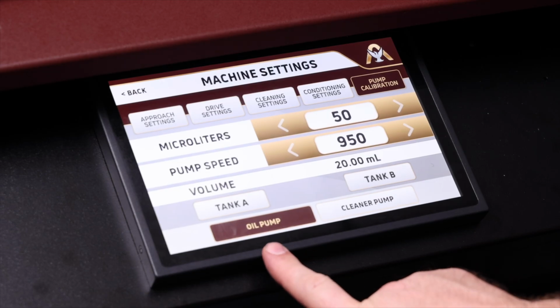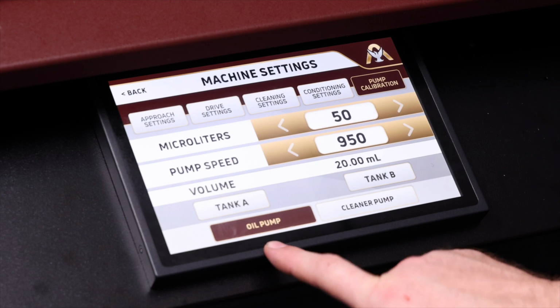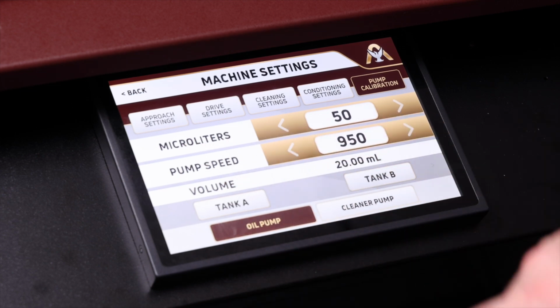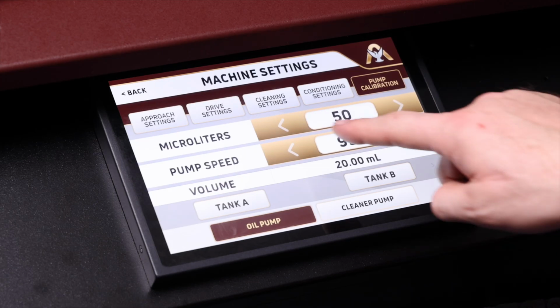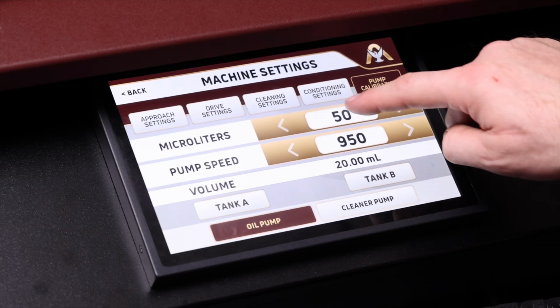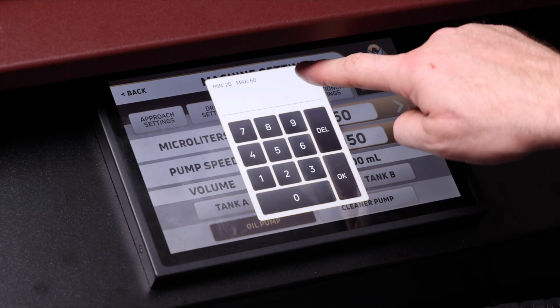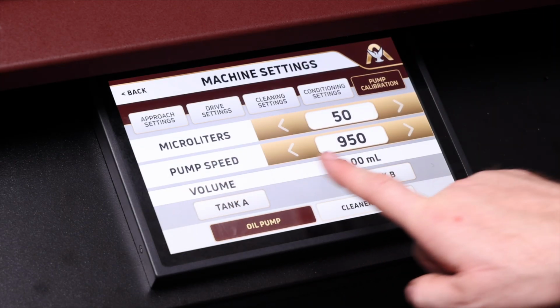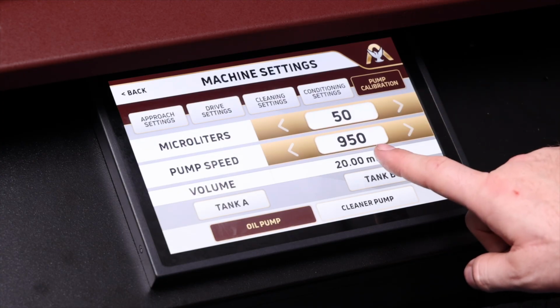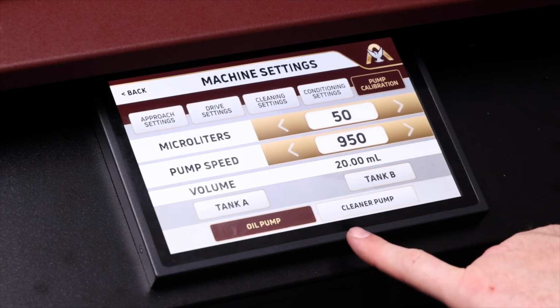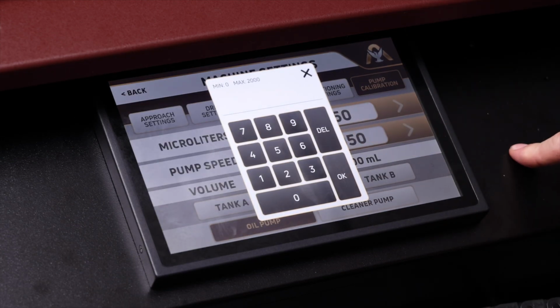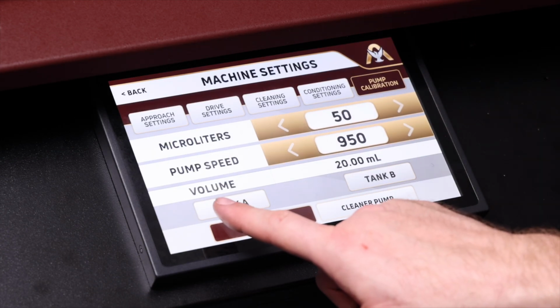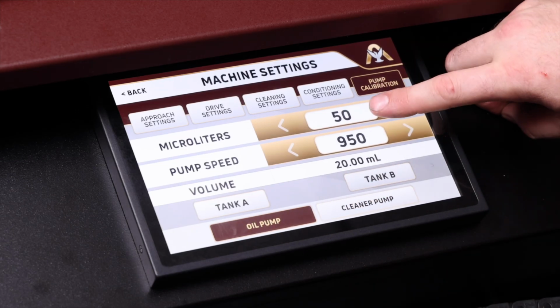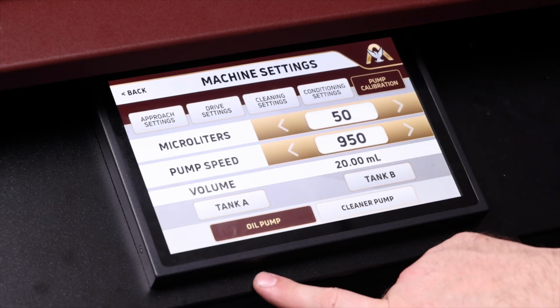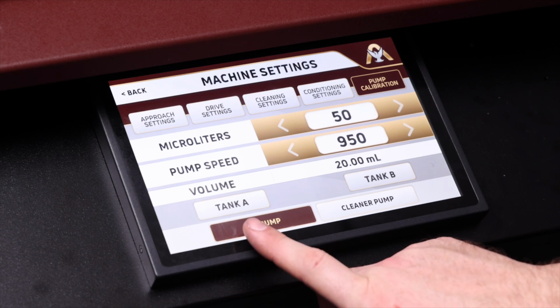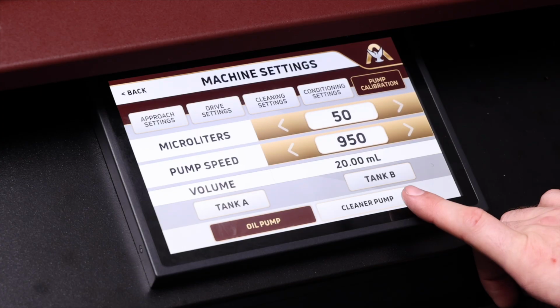At the bottom, we see oil pump selected, as well as our current microliters. You can change the microliter setting by using the arrows or by numeric keypad. Beneath that we have the pump speed with an adjustable analog value, also adjustable by arrow or numeric keypad. Below that we have the total oil volume for the set microliter. Beneath that we have the Tank A test button and the Tank B test button.